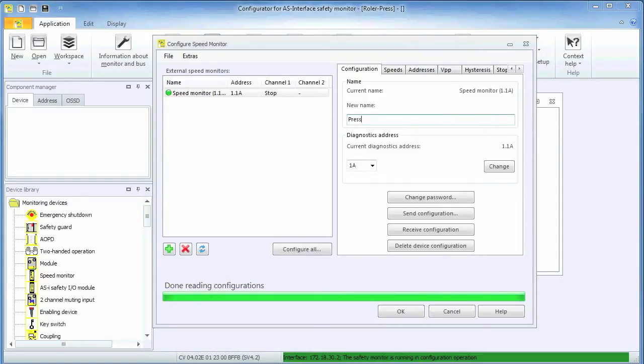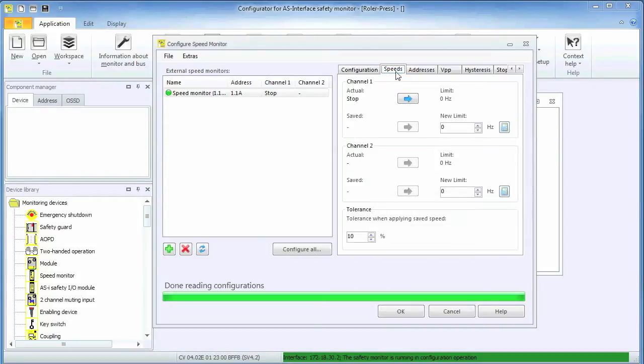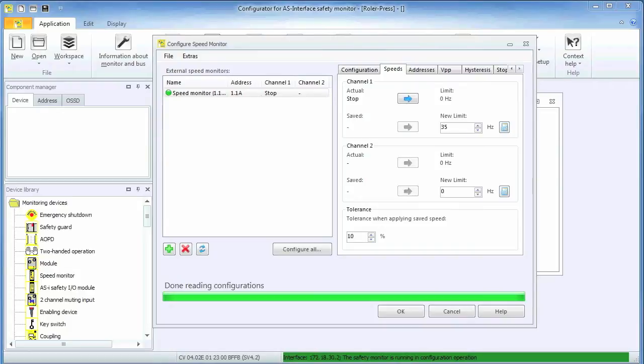Selecting the speed tab allows us to configure the safe limit speed. We have only one encoder connected to channel 1 and are thus going to enter a number only for channel 1. Entering 35 means that any rotational speed that results in an encoder output frequency of less than 35 Hz is considered safe.